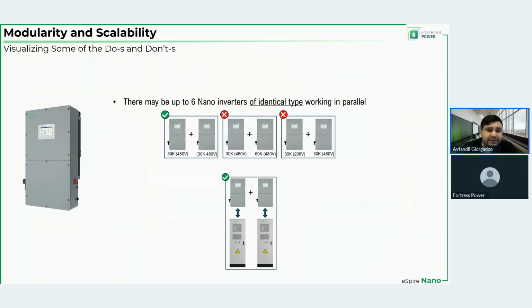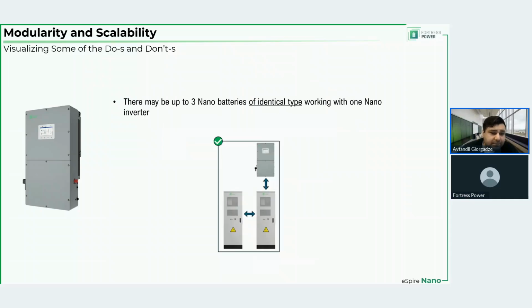Then let's visualize some of these. So there may be up to 6 nano inverters of identical type working in parallel. This is kind of what we're talking about, that you cannot mix them. And the battery banks or the battery units are not shared between the inverters. Each has its own. But up to 3 batteries may be connected to one inverter. And the way you do it is you connect the batteries to one another in parallel, and then the master battery connects to the inverter.